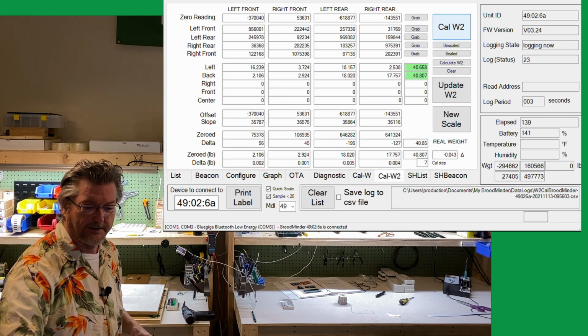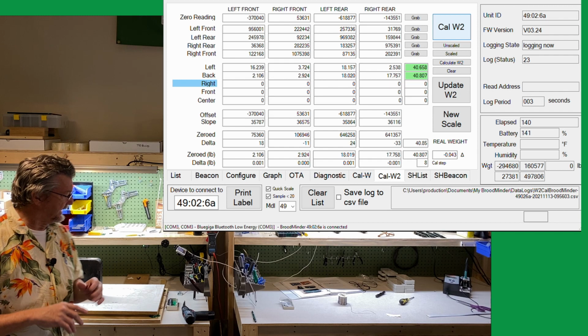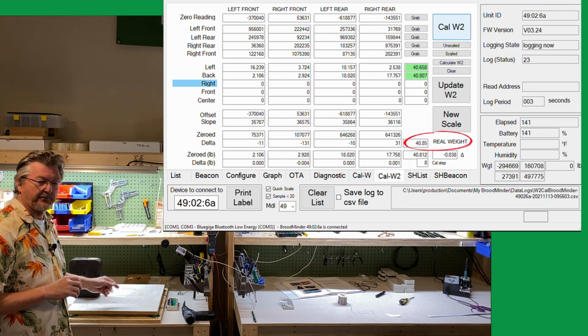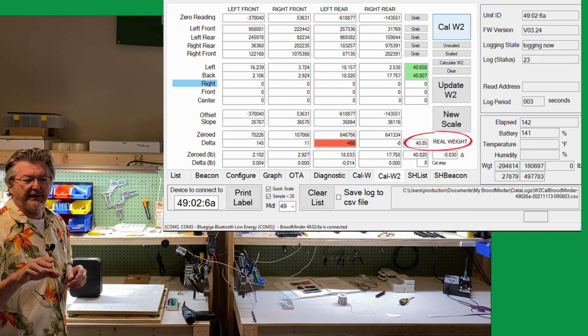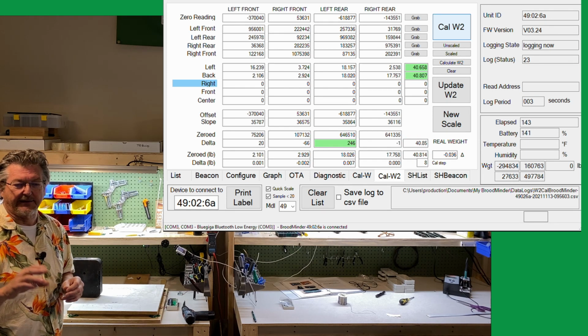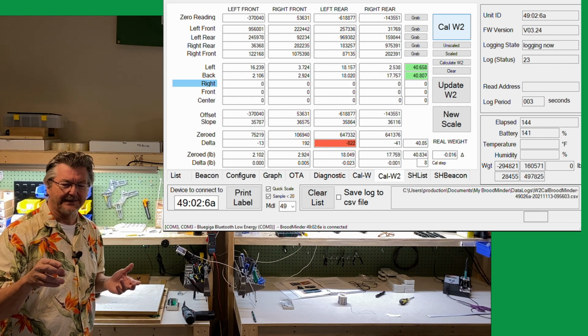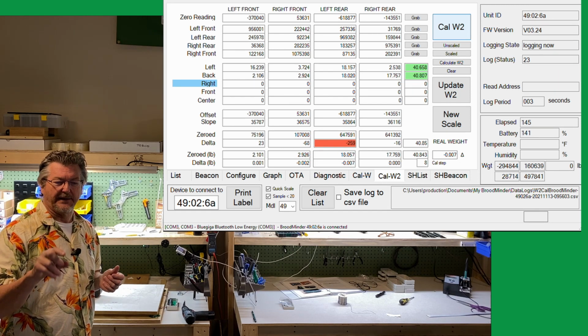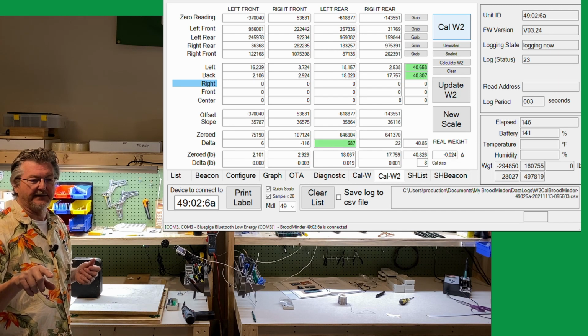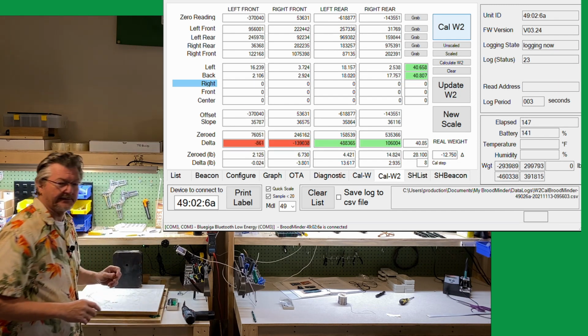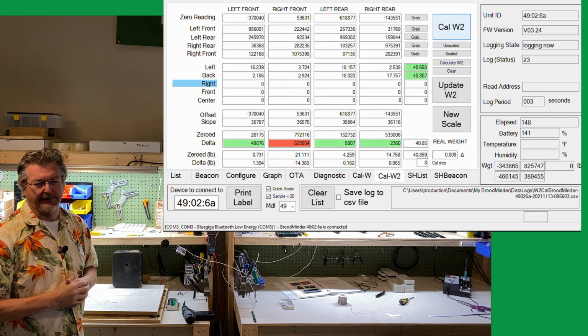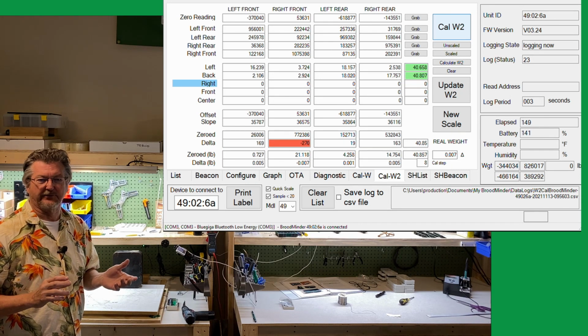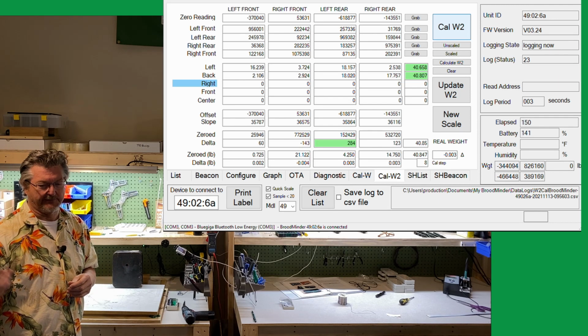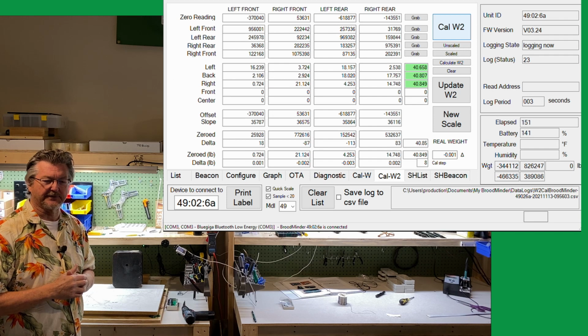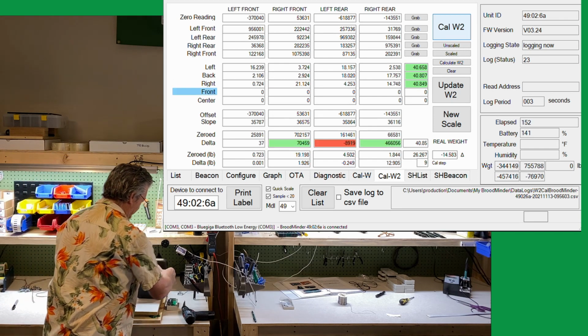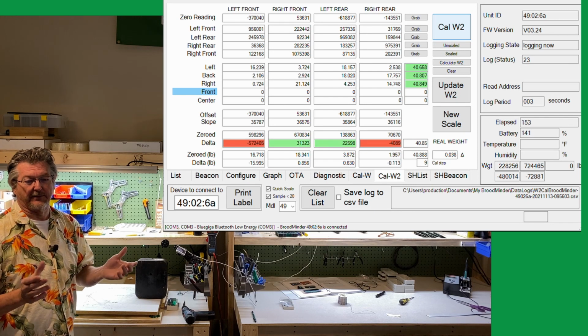Before you do all this, you enter the real weight, which I measured as 40.85. After it does calibration, it checks if we're within, I think, 0.2 pounds of that value. If so, it highlights green. If it's off, it highlights red, which is something we do for production to make it easy for our students who assemble these to tell whether it passes or fails.